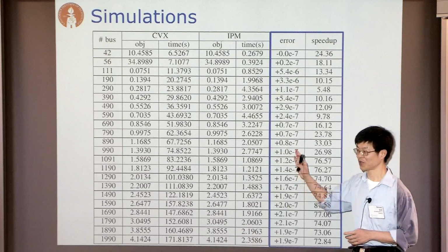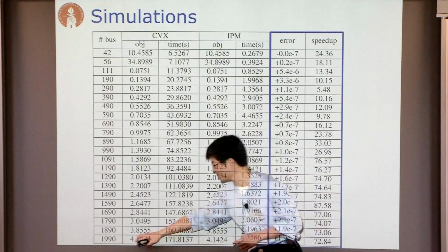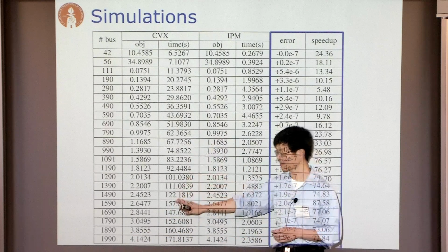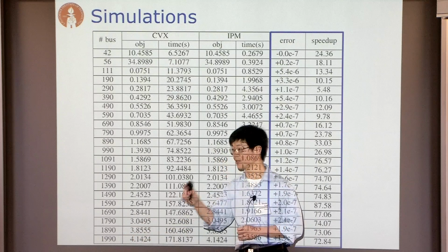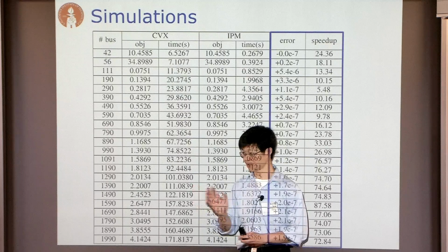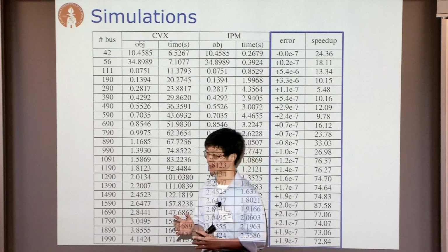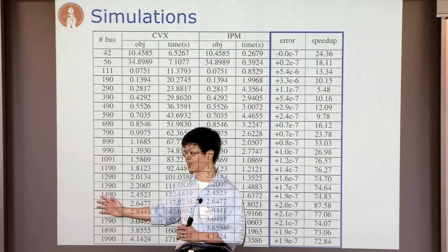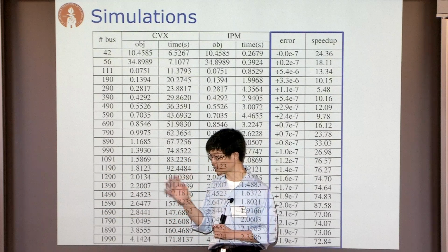Right. So this is actually one of the real networks in SCE, and therefore we have done a lot. For this particular set, we did look at solving the linear problem, but not using DCOPF. DCOPF is not suitable for distribution systems, but Baran-Wu's original model actually has a linear version, so we did use that.